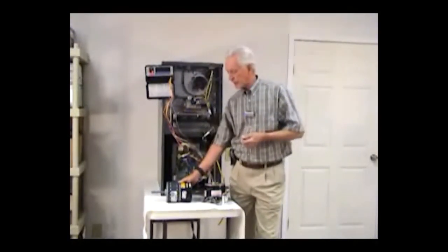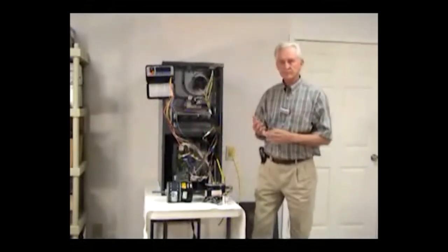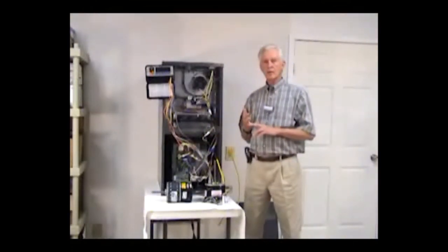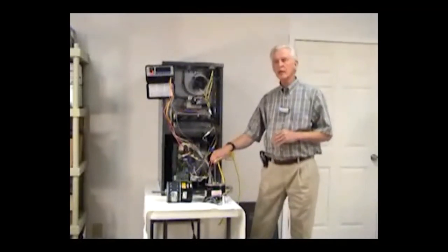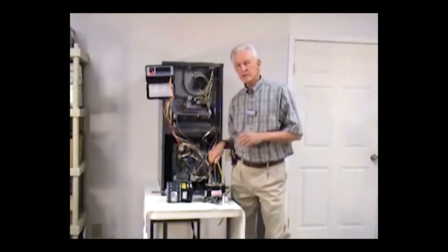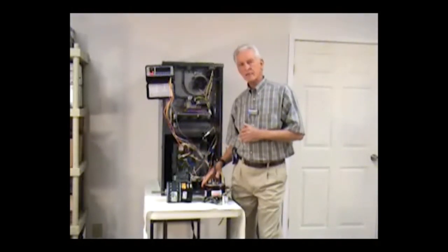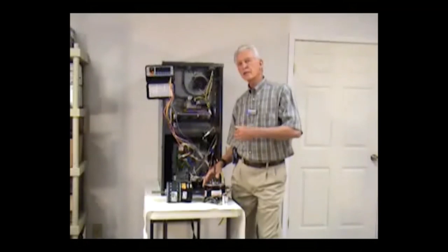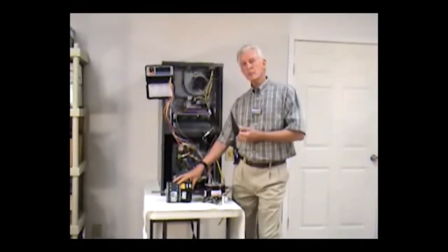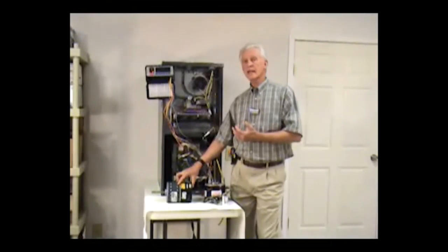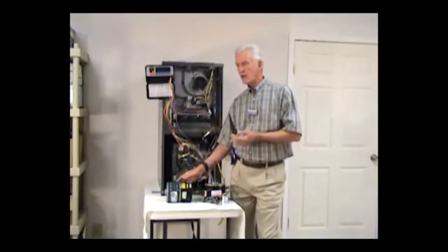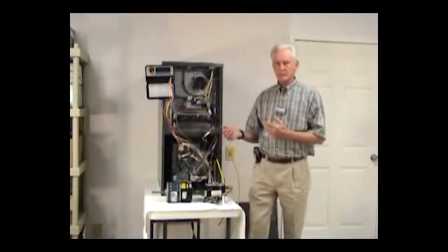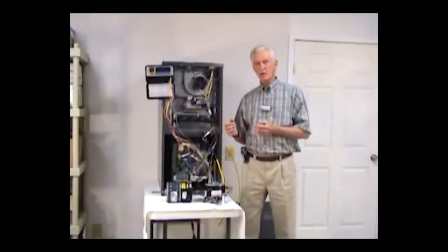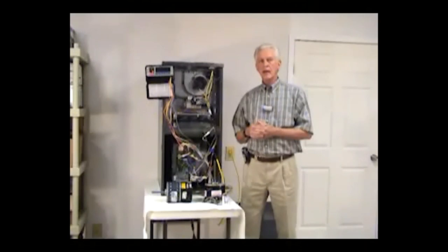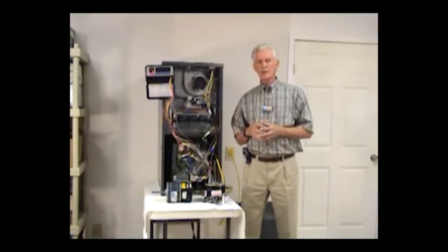In the process of doing that, we will vary RPM and we will vary amperage draw on the motor. We also reduce the number of motors that we would use from a horsepower standpoint, where quarters, thirds, halves, three-quarters, and one horsepower motors would be used for specific applications. Now these are broken down pretty much into halves, three-quarters, and in some instances for five-ton applications you may find one horsepower motors. That will allow us to operate in the ranges from zero external static pressure all the way up to a full inch of static pressure, and the amperage draw will vary with whatever that load is on that motor.